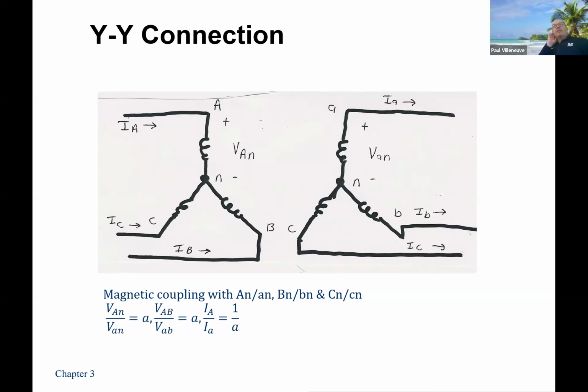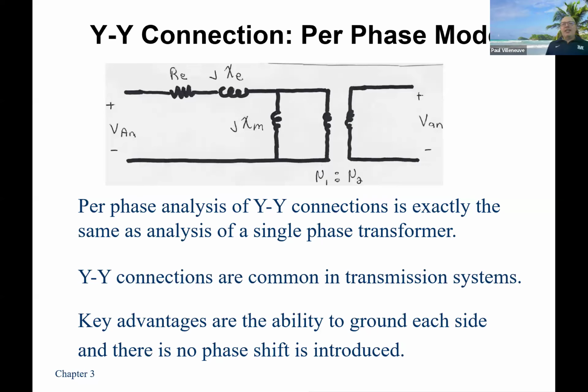Y-Y transformers are the most common connected ones. If you look at a pole top transformer configuration with three transformers, they're almost always connected Y-Y. Almost always. So here's our connection diagram or single-phase equivalent. No phase shift between primary and secondary, and we just have the turns ratio as specified. There are some advantages because you can ground both sides of the transformers, but that's not always an advantage. But the biggest thing is there's no phase shift.